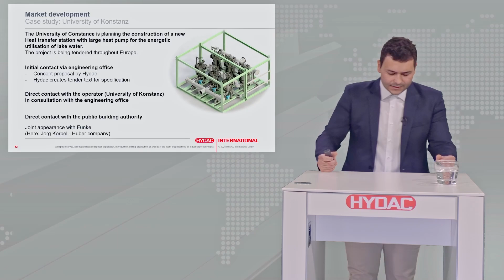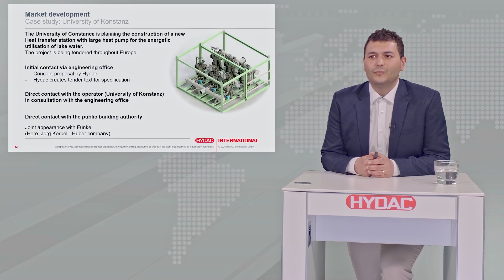Then I want to explain what we did. As I said, the University of Constance will build a heat pump with heat exchangers, and these heat exchangers need to be protected. What did we do as part of our test trials? We designed a 3-line concept: line A, line B, line C. Two lines always operating with 50% of the flow and one line in standby for redundancy.